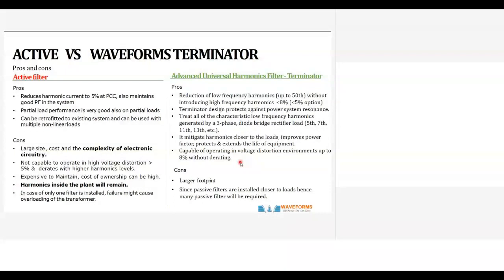It can be heavy, it can be a little larger, so you need to find space to keep them. These passive filters are installed closer to the load, hence many passive filters will be required. You may require a number of passive filters for different non-linear loads, so you will have to use your judgment to keep them to a minimum.